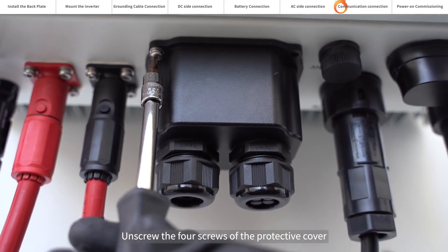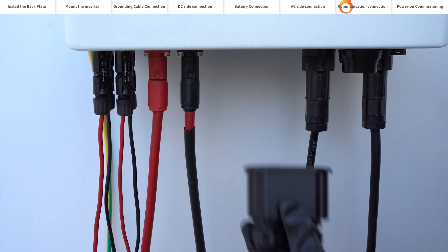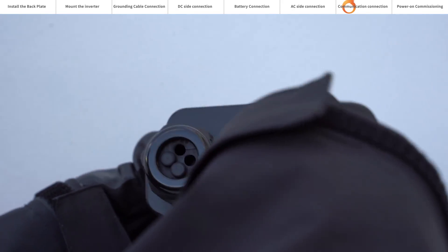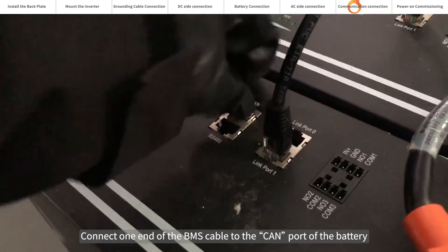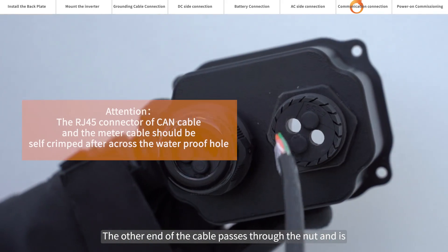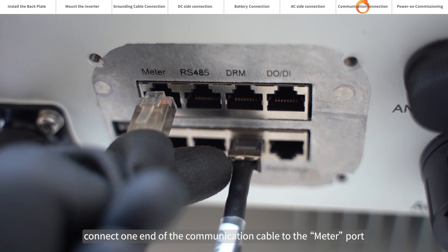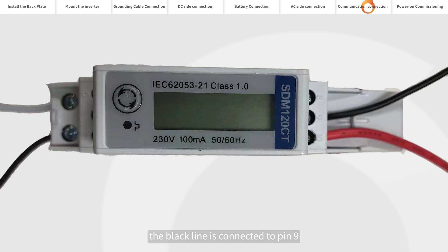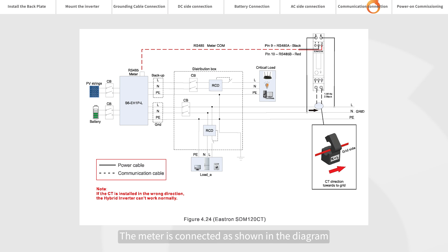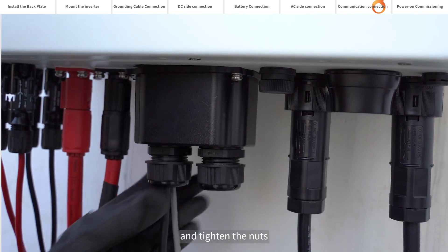Unscrew the four screws of the protective cover. Unscrew the nut and remove the black cylinder. Connect one end of the BMS cable to the CAN port of the battery; the other end of the cable passes through the nut and is connected to the BMS port at the bottom of the inverter. Connect one end of the communication cable to the meter port on the bottom of the inverter. At the other end of the cable, the black line is connected to pin 9 and the red line is connected to pin 10. The meter is connected as shown in the diagram. Close the communication cable protection cover, tighten the four screws, and tighten the nuts.